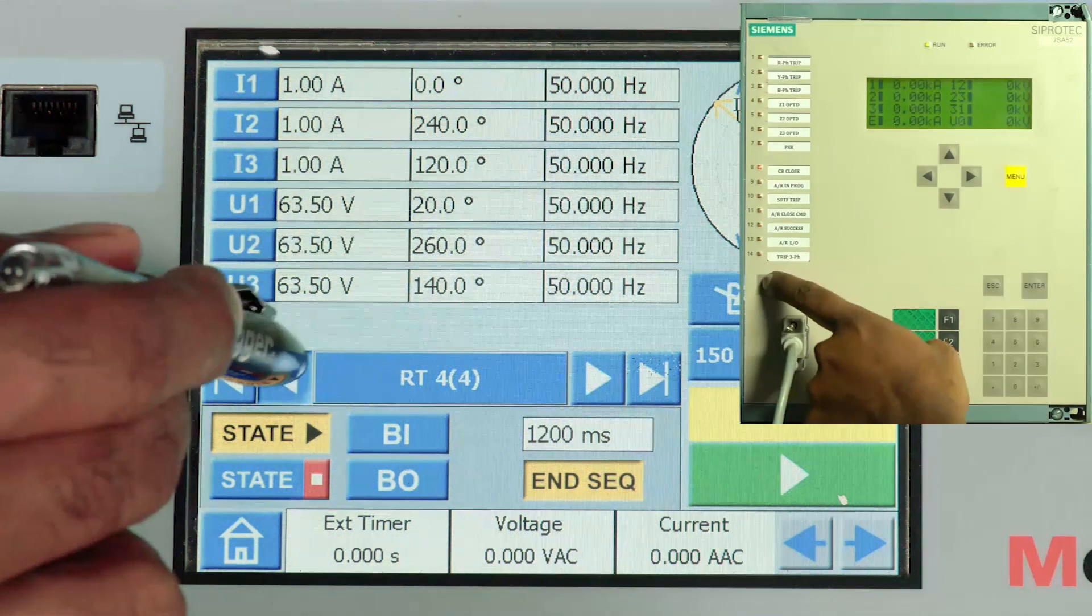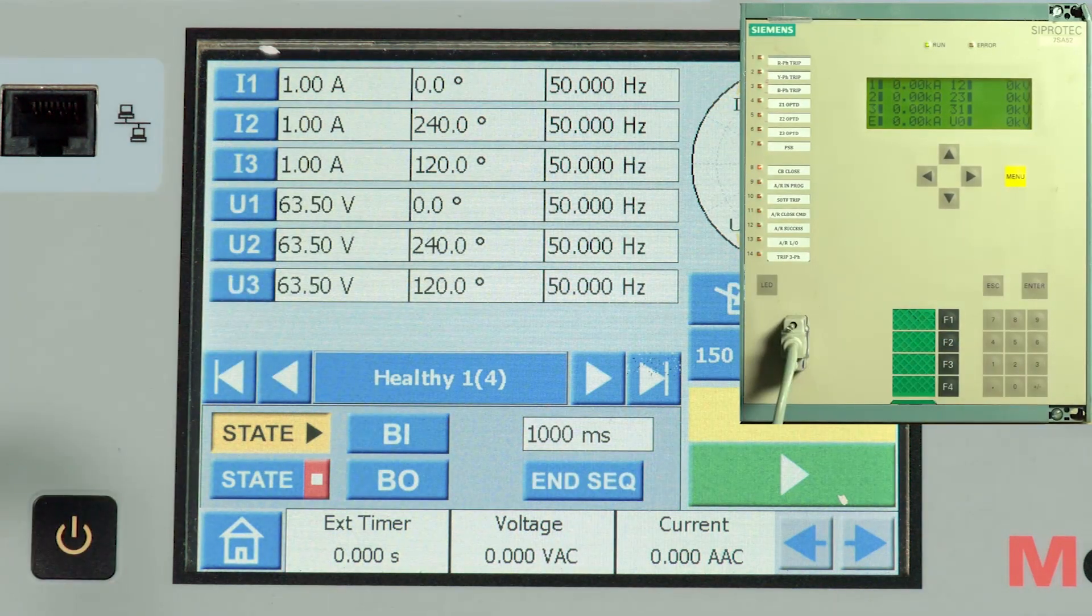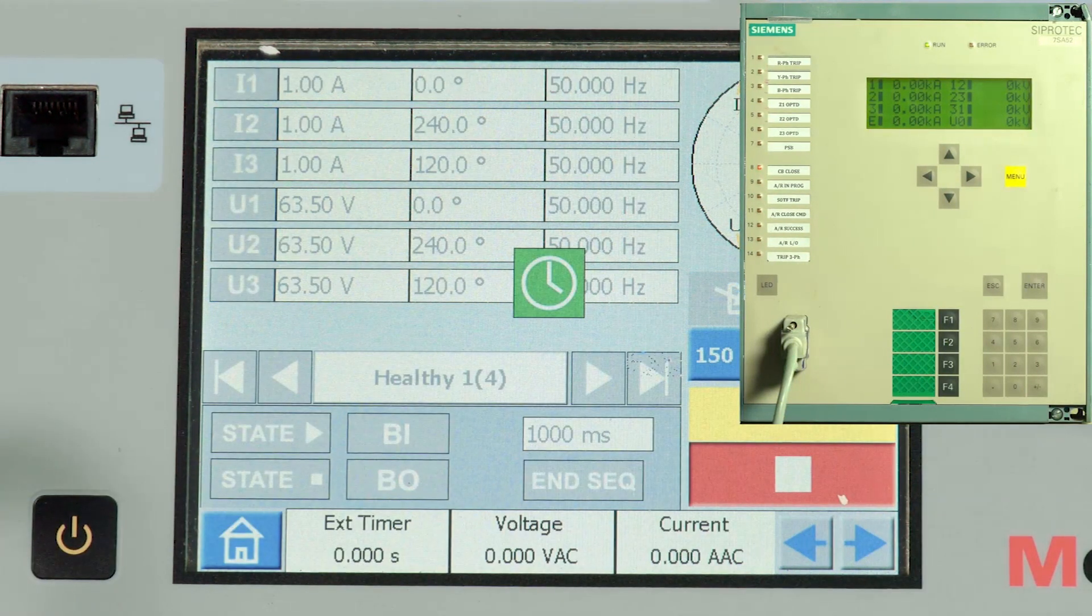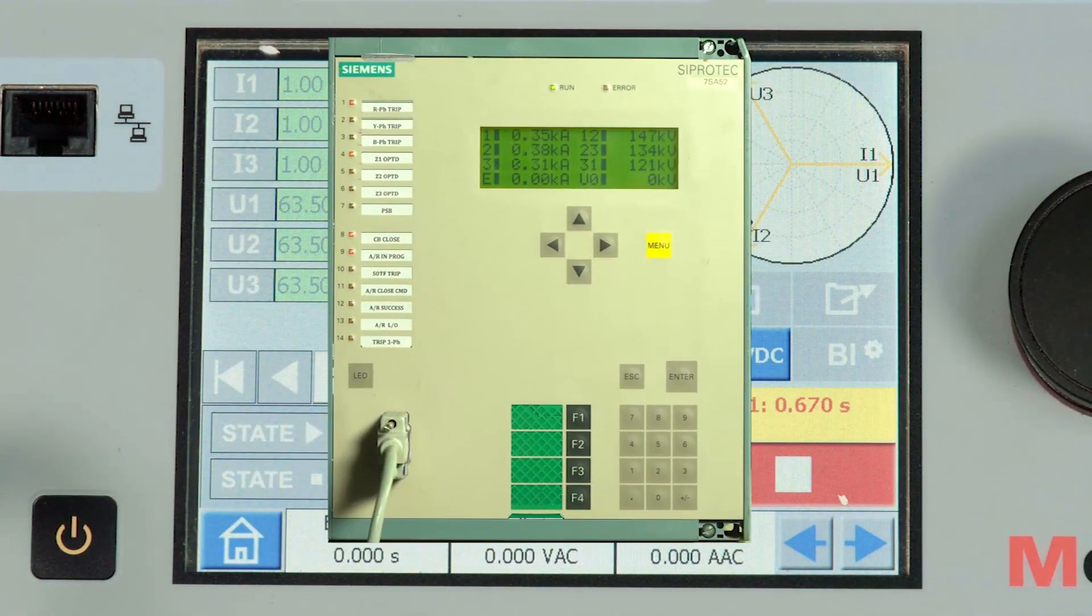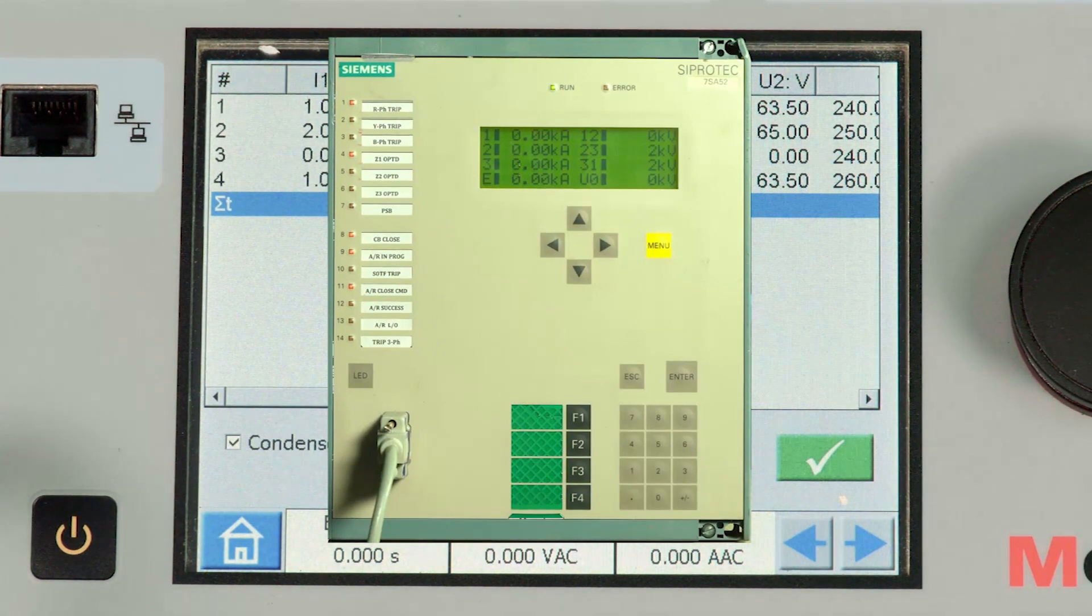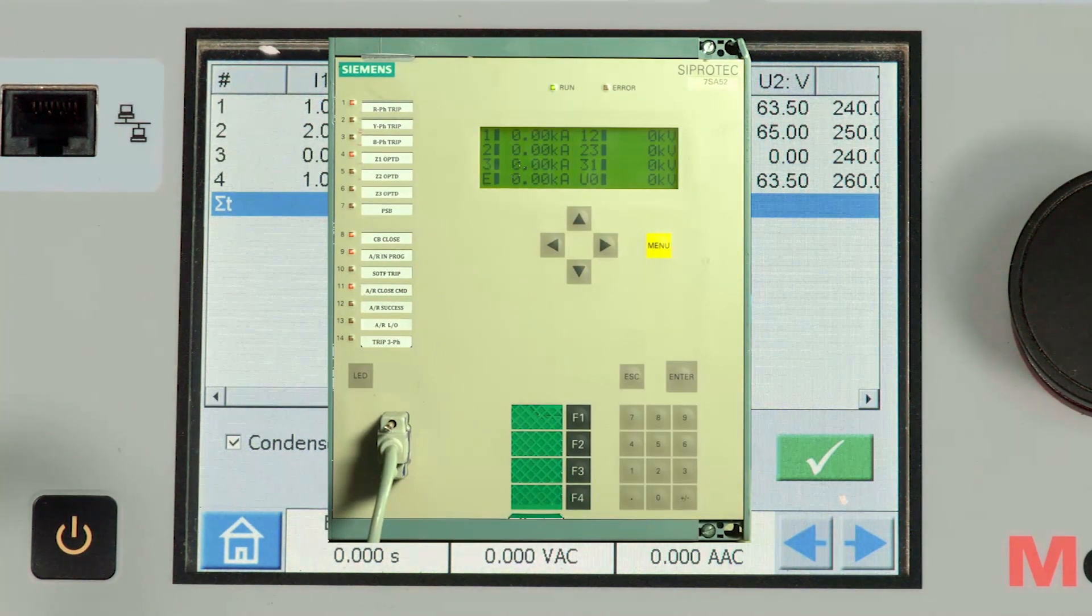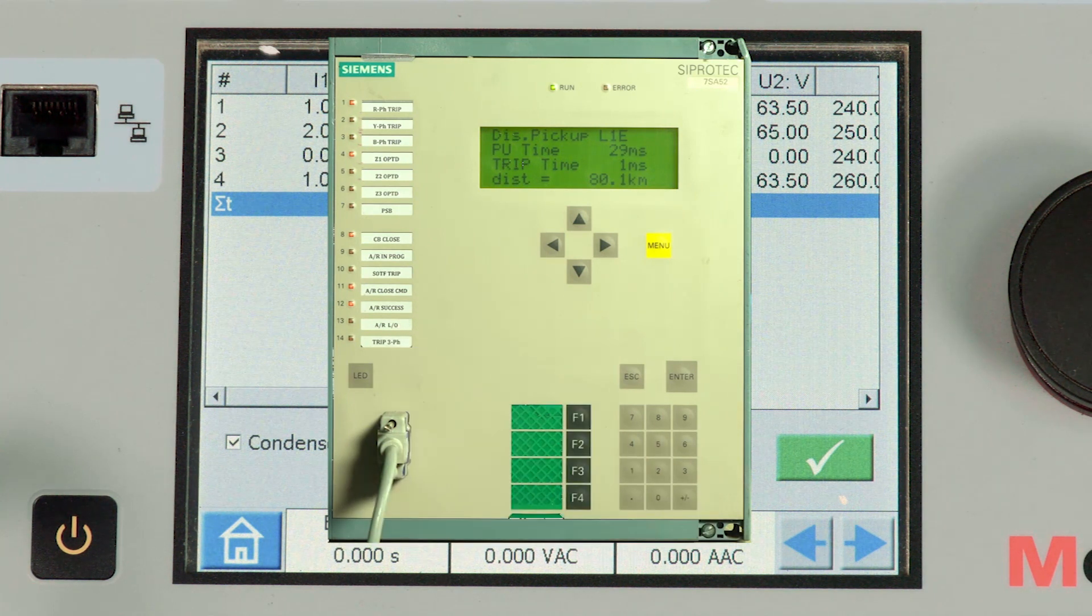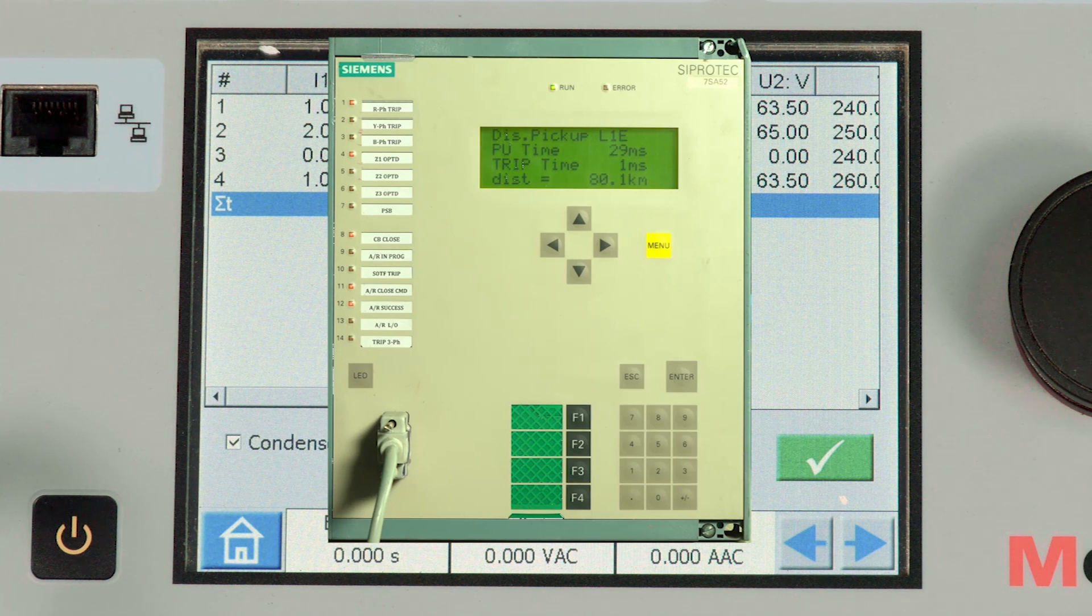So let me reset the relay and let me play the state sequencer. We can find the reading, the fault is identified, zone 1 operated, auto reclose in progress, close command initiated, and after the reclaim time we were also able to see the auto recloser success command.